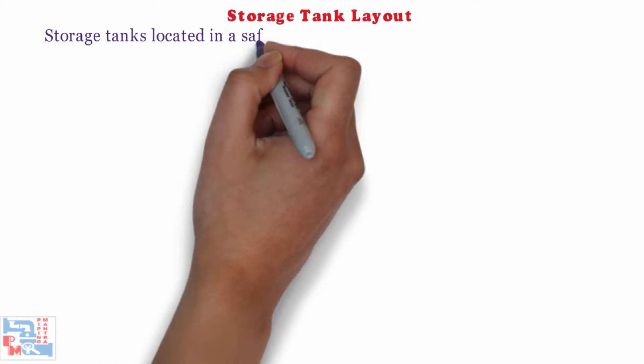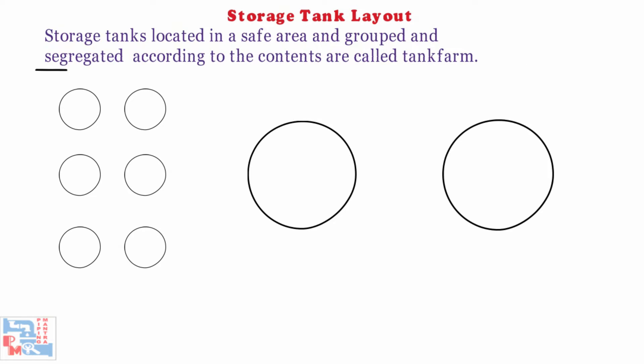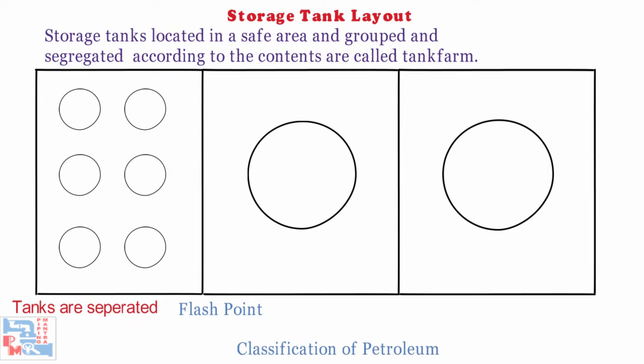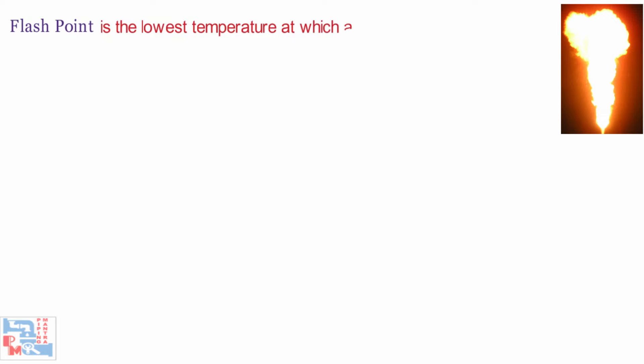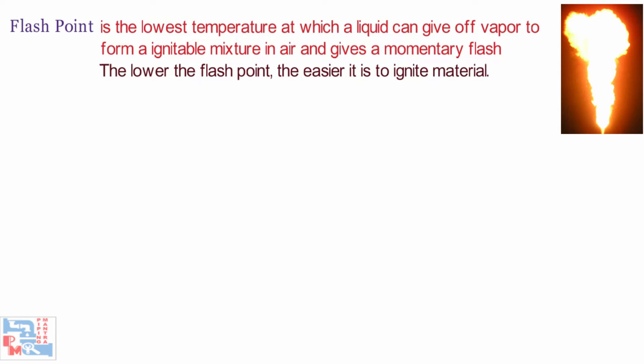Storage tanks located in a safe area and grouped or segregated according to their contents are called a tank farm. Tanks containing hydrocarbons should be separated according to the flashpoint. The flashpoint of any petroleum liquid is the lowest temperature at which a liquid can give off vapor to form an ignitable mixture in air and gives a momentary flash on application. The lower the flashpoint, the easier it is to ignite the material. Petroleum products are classified according to their closed cup flashpoints.